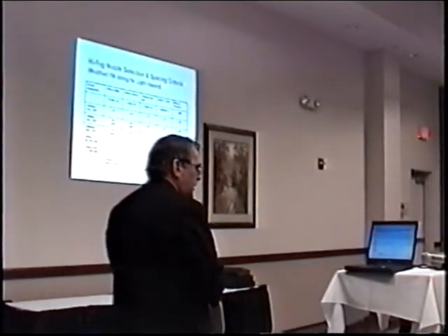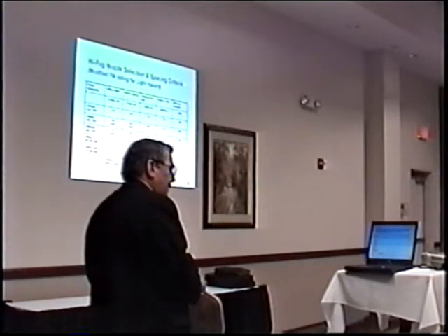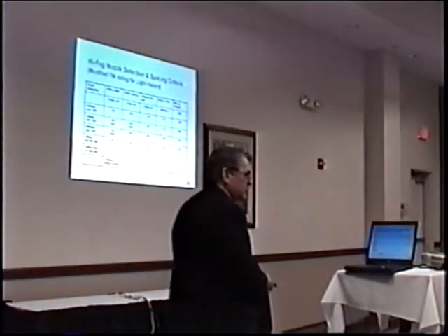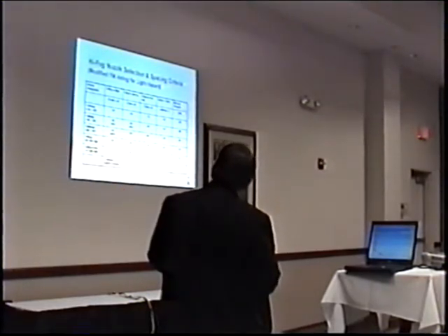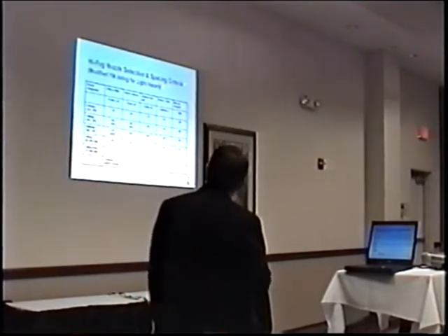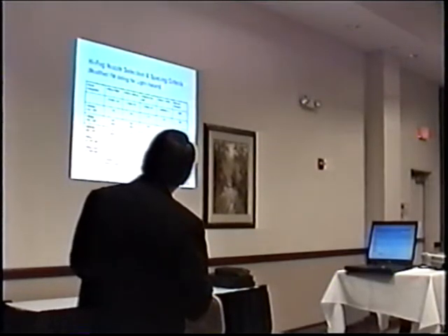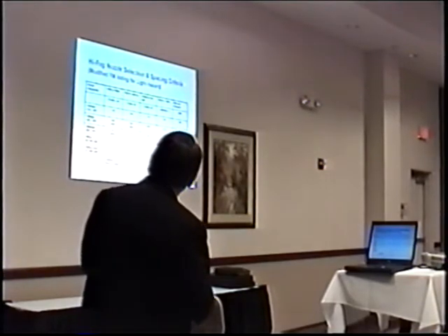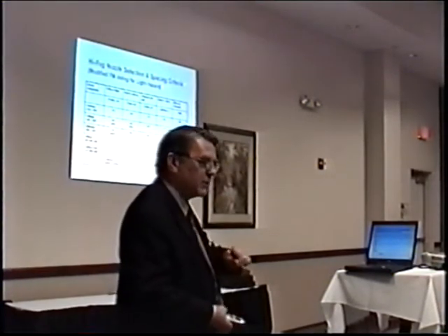we're trying to stay within the tested and listed aspects of some water mist equipment. NFPA 750, the standard for water mist systems, requires that all water mist systems be based on some fire testing and some approvals to the extent that they're available, and we were trying to do that. The Marioff company out of Finland had actually 1, 2, 3, 4, 5 different nozzle options that had been approved for light hazard occupancies. These ones were all good for 5 meter ceiling heights. These ones have been tested to about 8 foot ceiling height. And so I had a basic inventory of nozzles that were potentially suitable for this light hazard application.